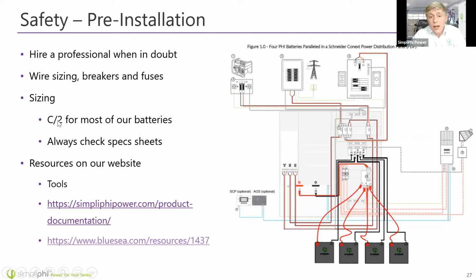Now, when you're sizing your battery portion of your system, the most important thing to follow, among other things, is the C/2 rule. So if you've got an 8,000 watt inverter, you need a minimum of 16 kilowatt hours of storage. So 8 kilowatt inverter, 16 kilowatt hours of storage. Just multiply by 2. So that means you need 5 batteries for an 8 kW inverter. The reason for this is because our batteries can discharge at C/2, meaning you can charge and discharge them fully in 2 hours. So if you've got a single 3.8 kilowatt hour battery, you can discharge that at 1.9 kilowatts continuously.